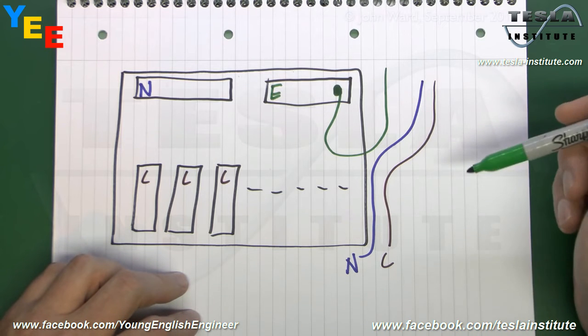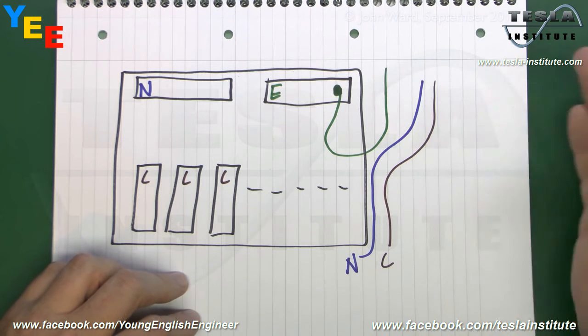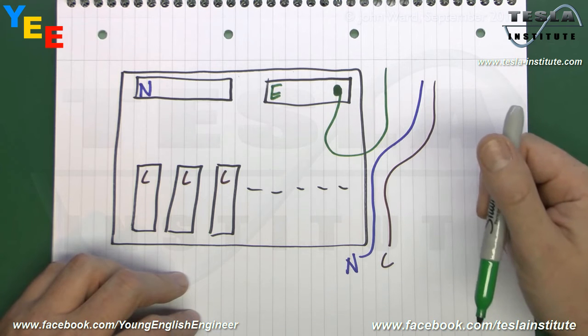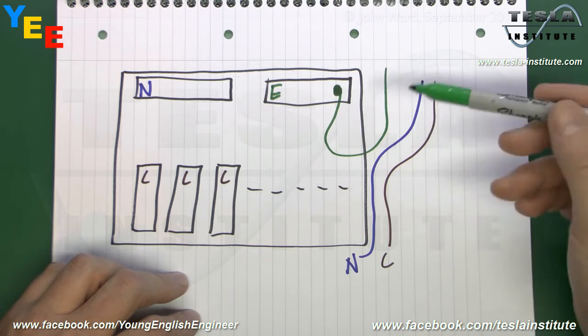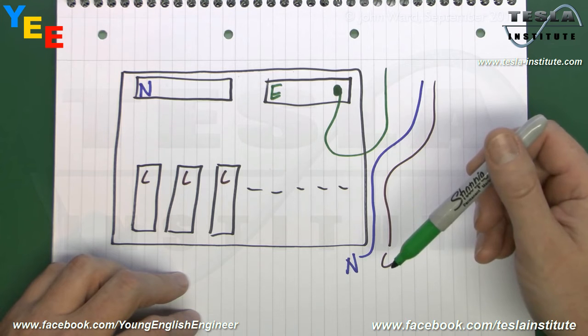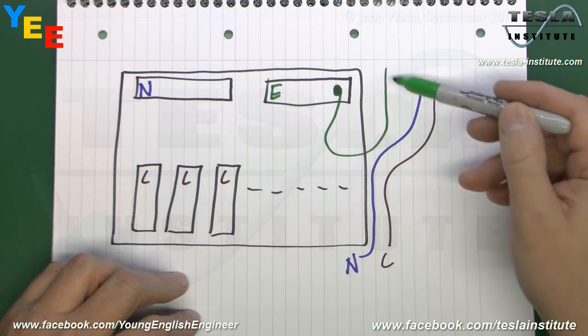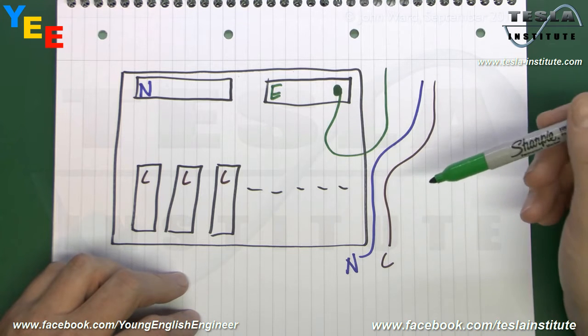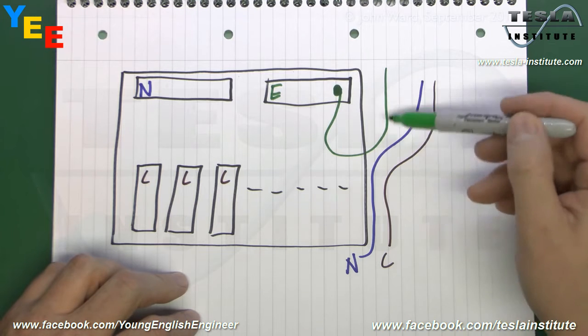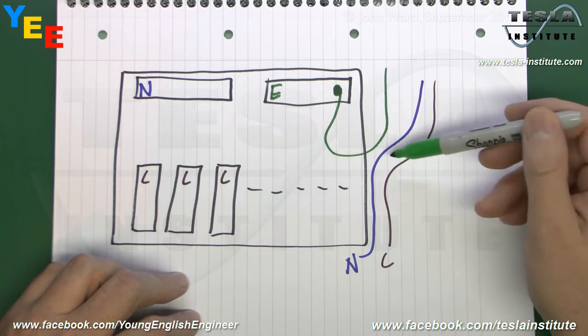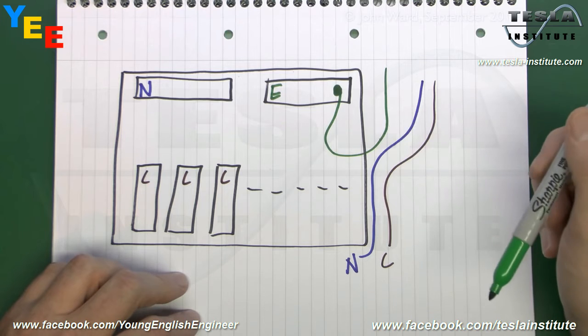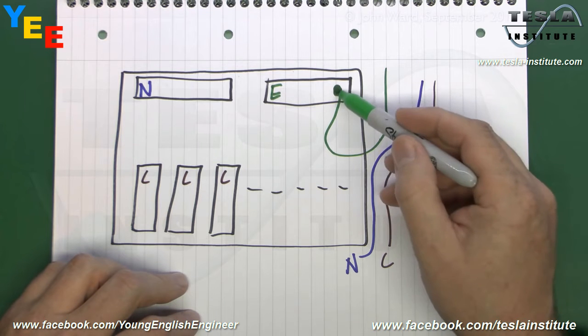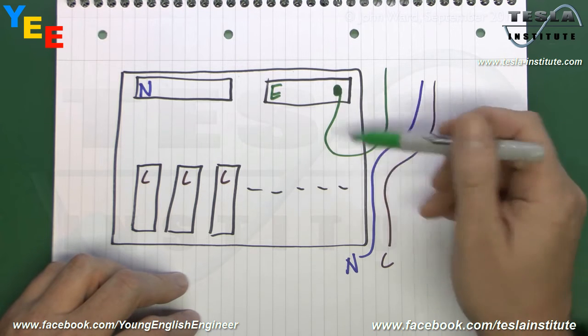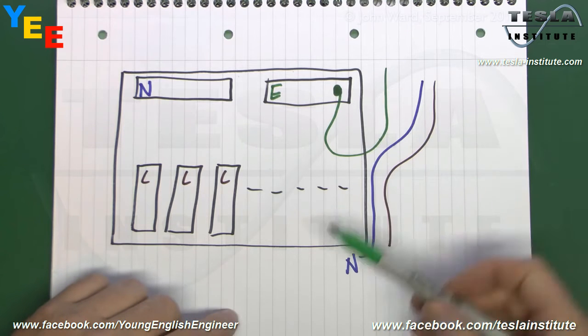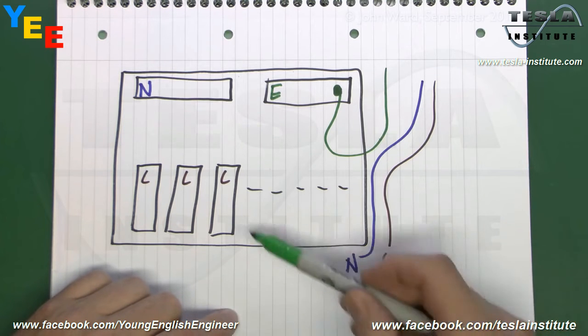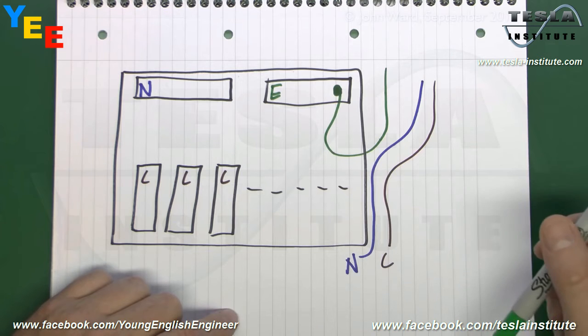And similar things could occur, say, with an immersion heater or something that had gone faulty and it was earthed by virtue of the piping or the metal pipework. But of course, if this for some reason hadn't been connected correctly or something, there will still be a fault there, but it wouldn't necessarily show up as a fault between the cable here and the cable there. So the protective conductor or earth conductor needs to remain connected to the installation earth, but the other 2 there do need to be removed from the appropriate places in the consumer unit.